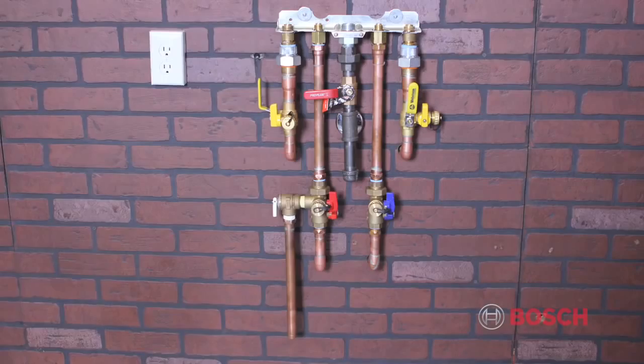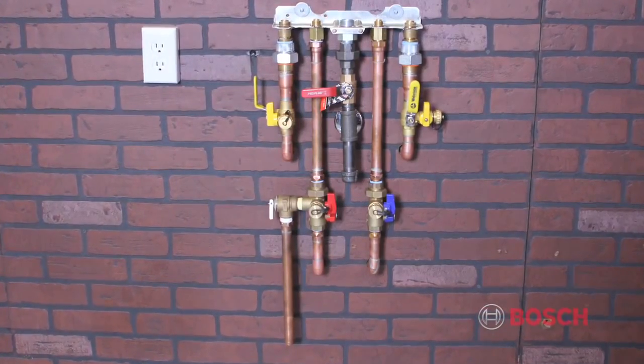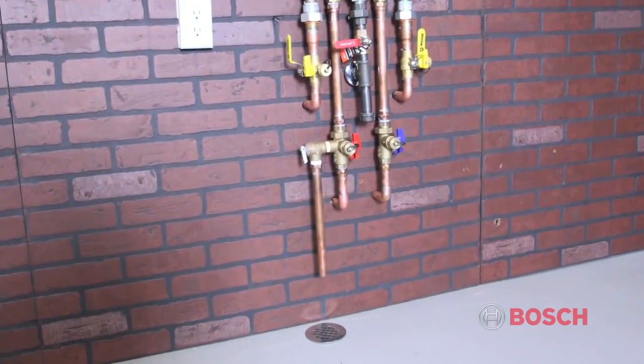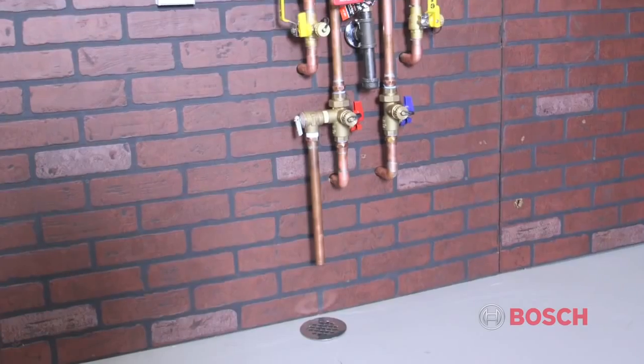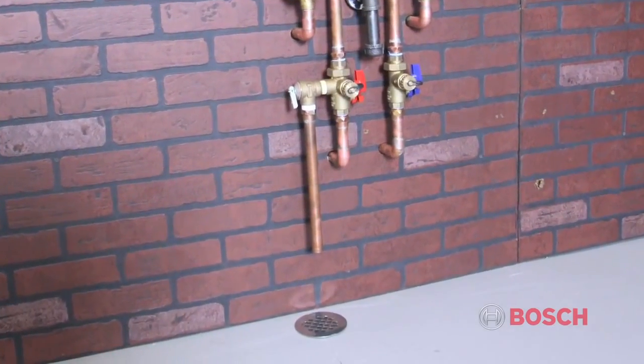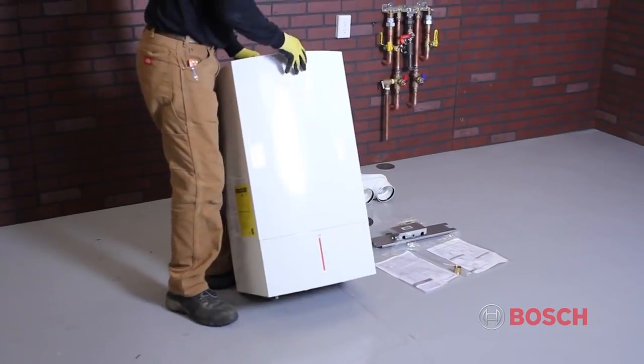A temperature and pressure relief valve is included with the service valve kit. Plumb this valve so that it is within 6 inches of a floor drain or per the requirements of your local code. The next step is mounting the unit to the wall.